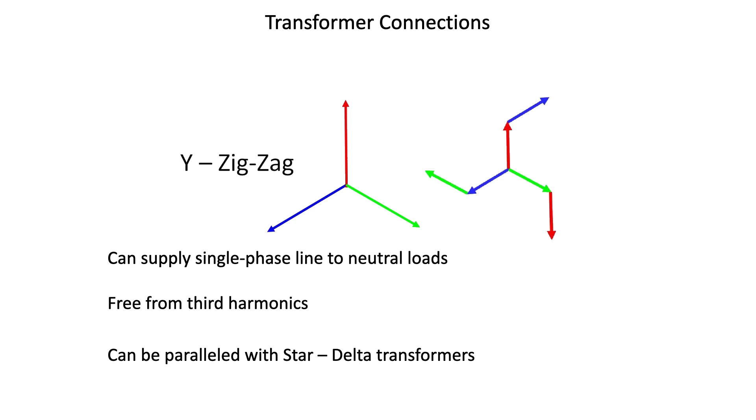The phase relationship of the phase to phase voltage, and we're looking at the red to white in this case, is the same as a star delta transformer. That is, there's a 30 degree phase shift from primary to secondary, yet a neutral connection is available for relaying and other single phase loads.